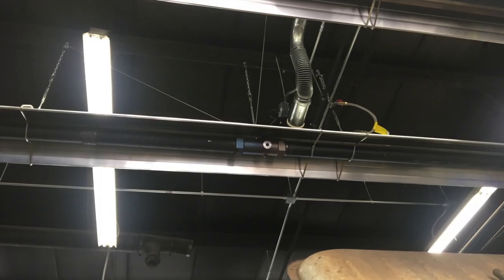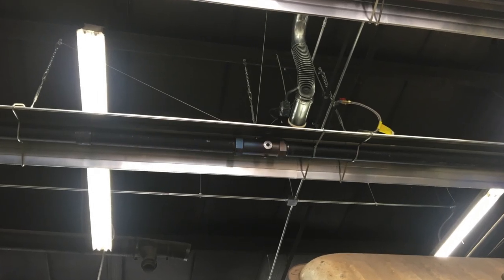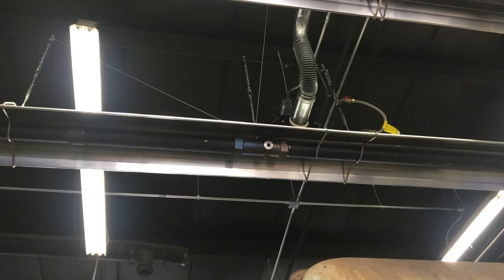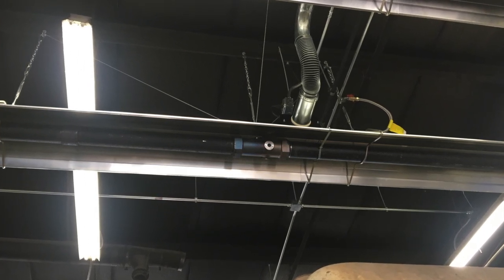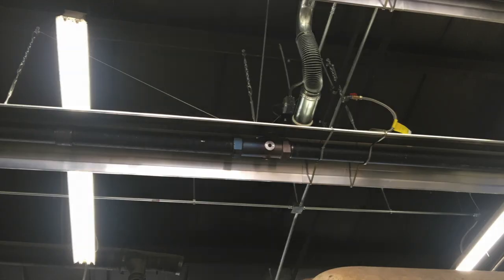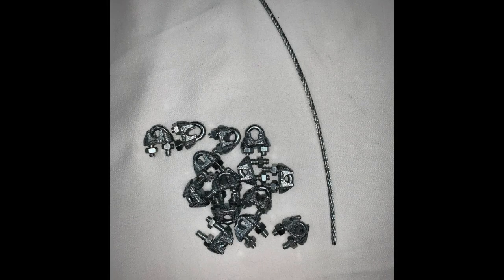Sway bracing can be put on before or after the reflectors are on. Drill or wrap around the 1/8 inch wire at the purlins at a 45-degree angle. Use 2 wire clips per end. The other end needs to go through the lower spring hook after the turnbuckle.